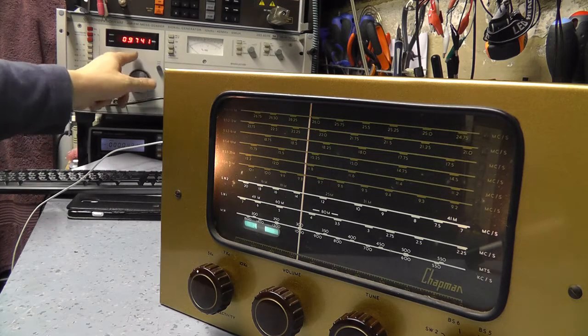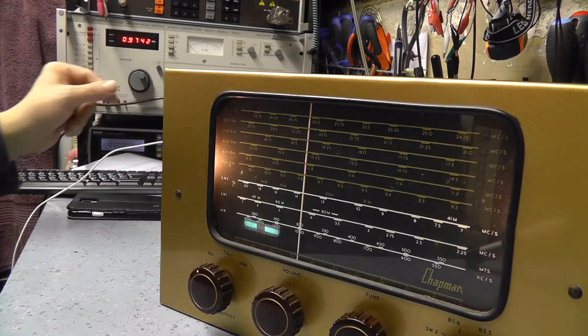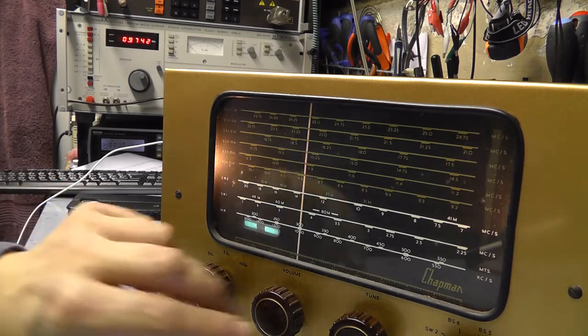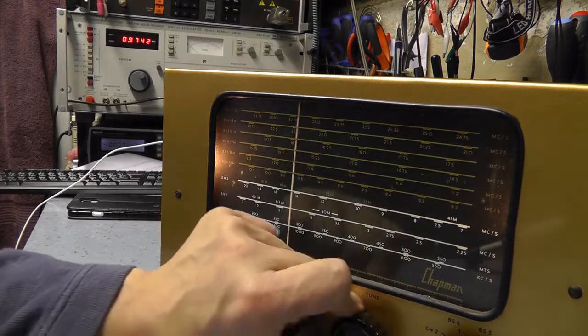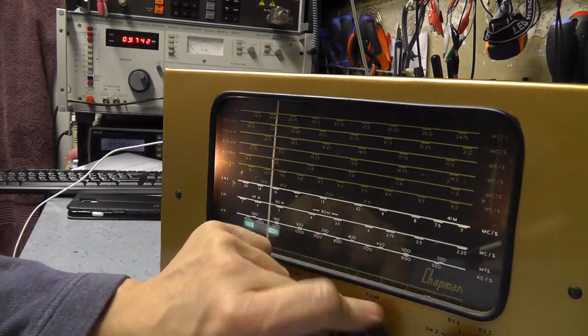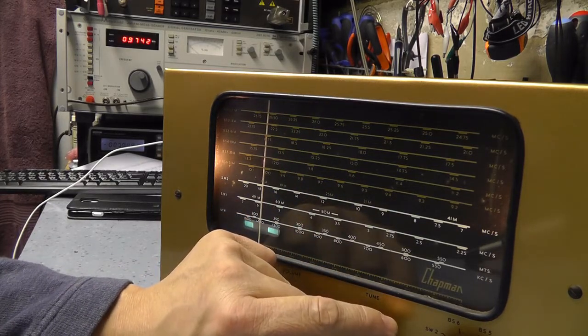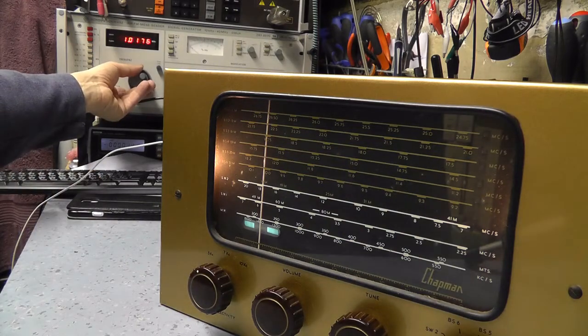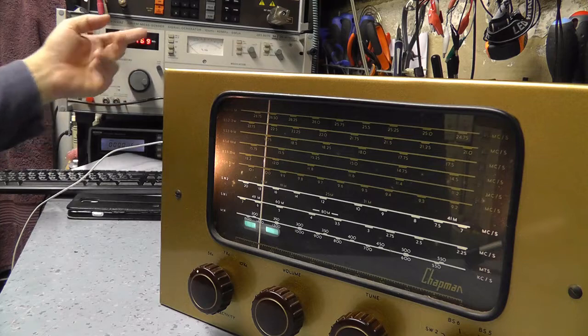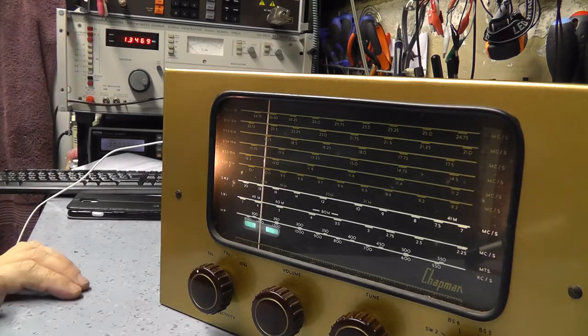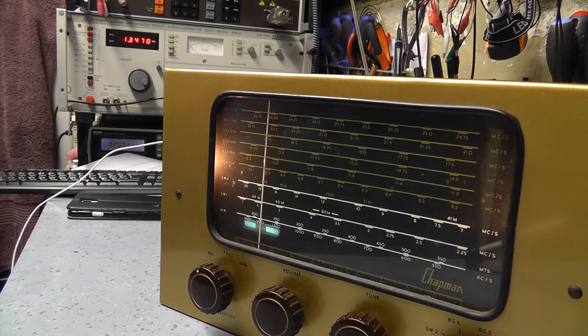Okay, we're slightly out, but it's not too bad. It's staying fairly linear. It's 974 kilohertz. Oh, that's volume. And then let's go to 1400 kilohertz. Tune to 1400 kilohertz, 1.4 meg. Okay, so there is a slight scale linearity problem there, and that will be one of the first things to check to see if we can improve on that.